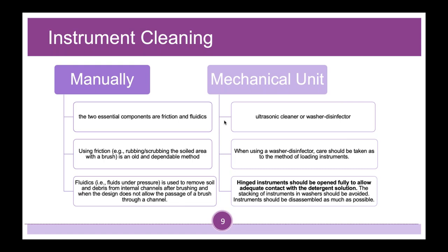For your mechanical unit, you're going to have ultrasonic cleaners or washer disinfectors. When using a washer disinfector, care should be taken as to the method of loading instruments. The loading process is extremely important. Hinged instruments should be opened fully to allow adequate contact with the detergent solution. Stacking of instruments in washers should be avoided, and instruments should be disassembled as much as possible so that as it goes through the washer disinfector, it can get into all of the nooks and crannies.